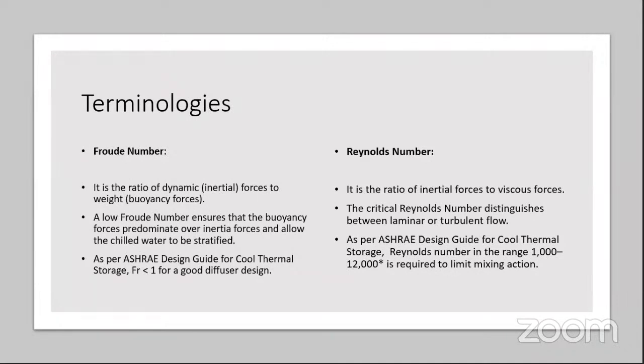Well, Froude number is generally the ratio of the inertia forces versus the buoyancy forces. A low Froude number ensures that the buoyancy forces predominate over inertia forces and allow the chill water to be stratified. As per ASHRAE design guide for cool thermal storage, Froude number should be less than 1 for a good diffuser design.